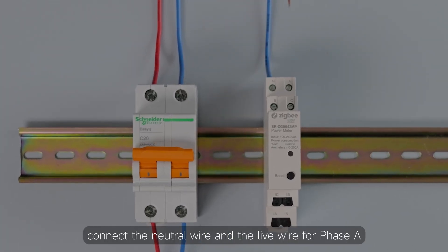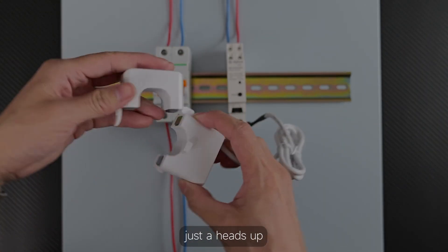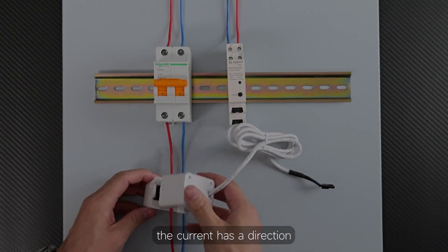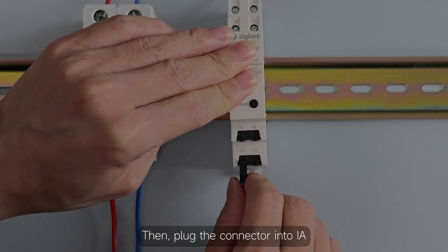To set it up, connect the neutral wire and the live wire for phase A. Make sure to thread the current transformer around the live wire. Just a heads up, the current has a direction so if it's wrong you can flip it if needed. Then plug the connector into IA.